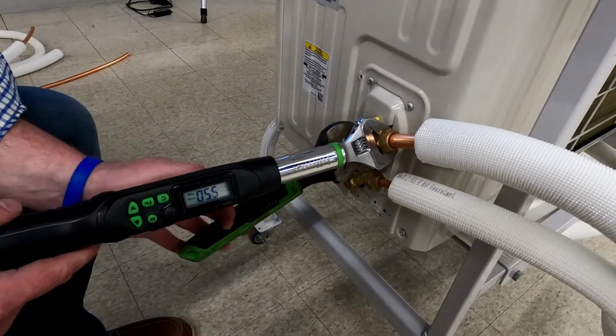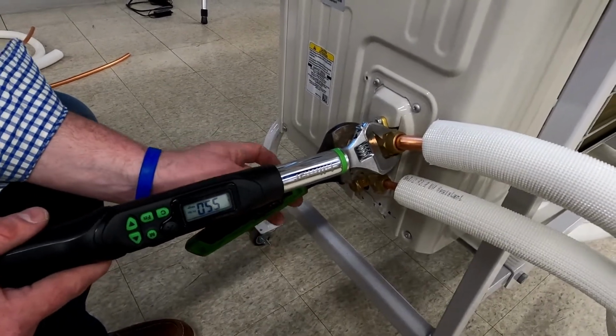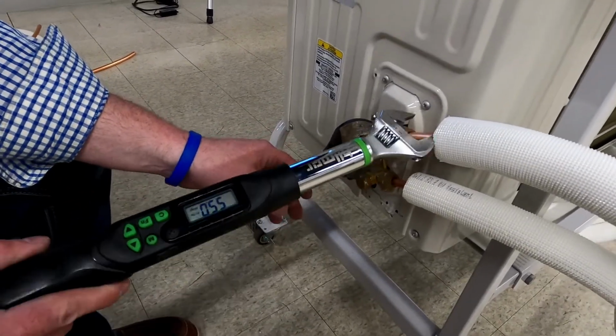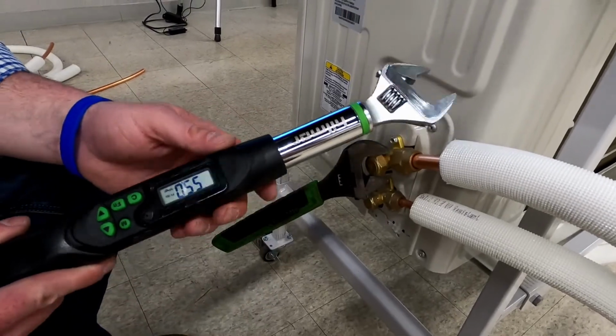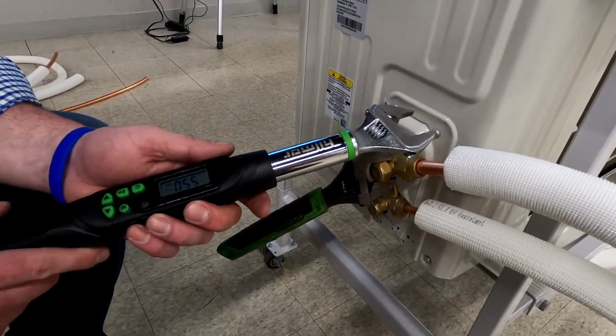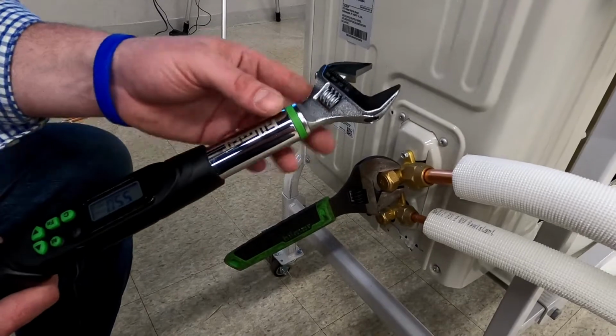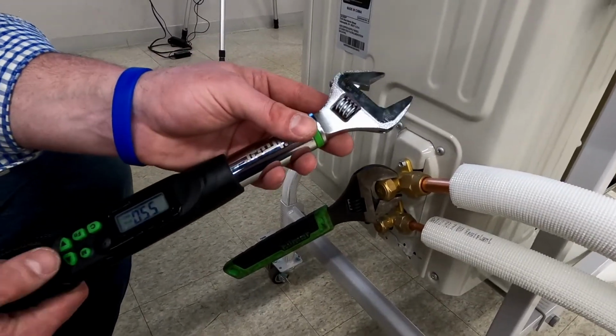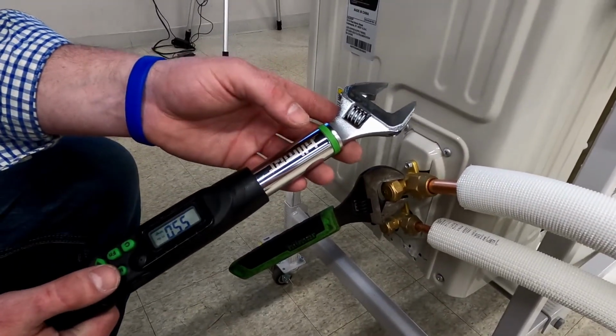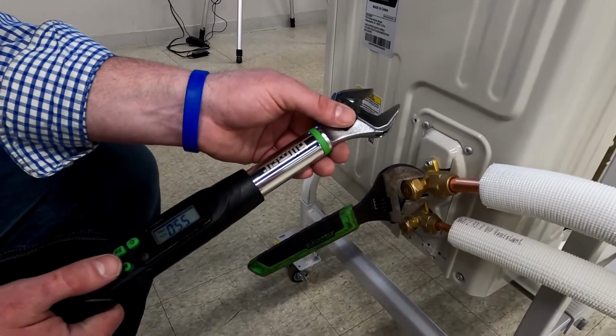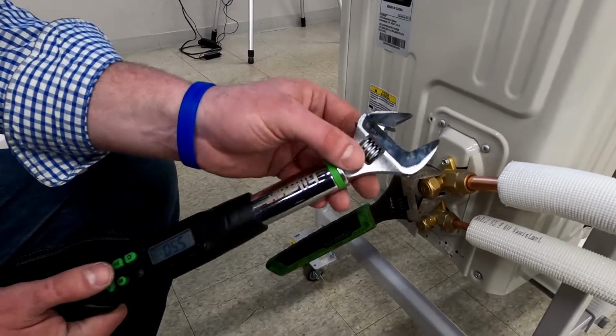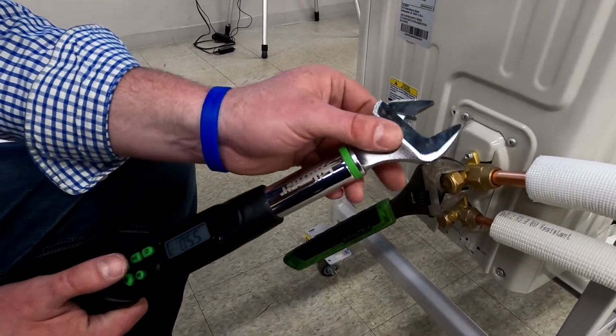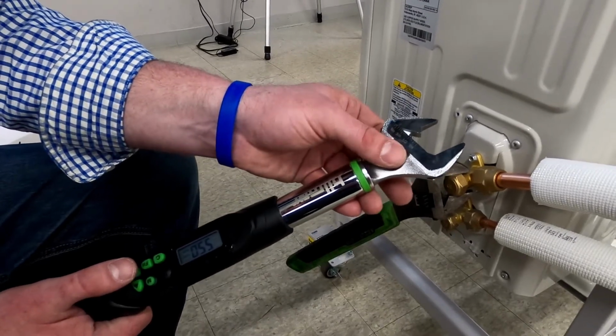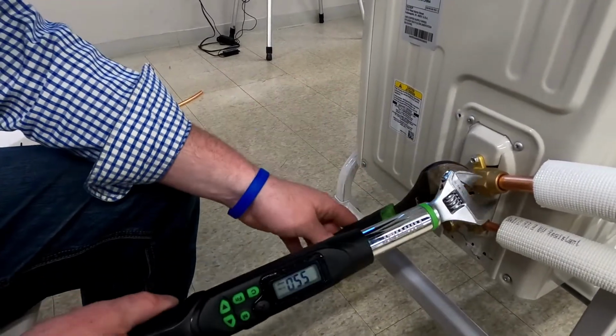All right, so for this example, we have the Hilmor digital torque wrench. I've already set my maximum torque per the specification in the manual. One nice thing about this tool is that you can save in the memory numerous torque settings depending on the size of pipe that you're connecting. Another nice part is that it's adjustable, so you don't have a bunch of different parts that you have to change out.